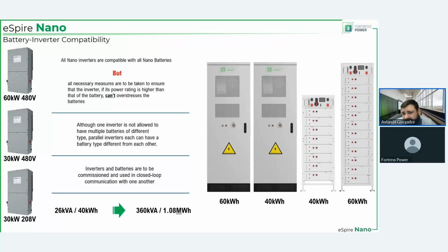In some rare cases, the battery storage system could be requested to be undersized, in the sense that you will have a 60 kilowatt inverter but, let's say, a 40 kilowatt hour battery, so the inverter's power input and output capabilities are greater than those of the battery. Well, that is a risk, especially if you're doing a backup. There is a risk that the inverter will overcharge or over discharge in terms of current to the battery. Yes, the battery does have protection mechanisms against that, but there's not much protection against the load, because when the load turns on, it instantly requests power from the inverter. The inverter passes that request on to the battery, and the battery has to respond.